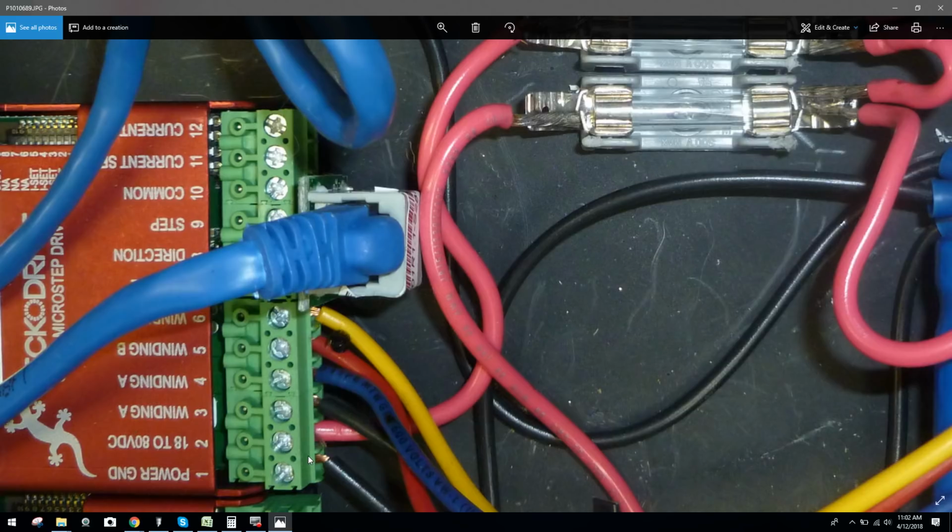You can, of course, use ferrules. That's fine. Ferrules are really designed to be used when you're removing things on a more regular basis. If you're constantly removing things, you're going to have issues. Tinning cables works out extremely well, especially when you're using about an 18-gauge to 16-gauge cable. You're fine, as long as you're not tightening these bolts like you're tightening lug nuts on your BMW. You're going to be perfect. I can't emphasize that enough.